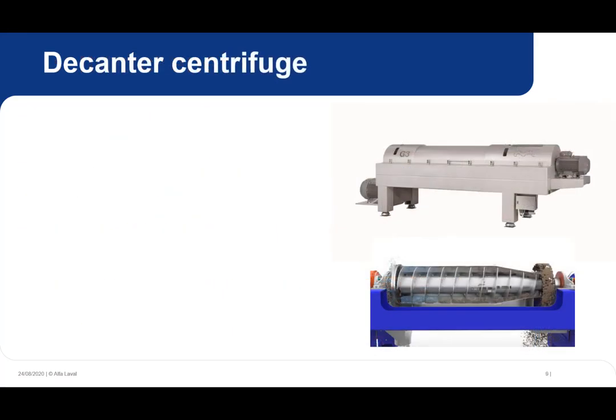A decanter centrifuge is the final thickening method we'll talk about. It operates by means of a horizontal cylindrical bowl equipped with a scroll conveyor that rotates at a high rate of speed. The feed enters a centrifuge through a stationary inlet tube in the center and is accelerated into the bowl by a distributor. We call this distribution area the feed zone. The bowl and conveyor rotate at a slightly different speed, allowing the conveyor to push cake solids up the inclined cone of the bowl, also called a beach, and out, while the clean centrate exits the other end of the centrifuge. The components exposed to liquid are often protected by replaceable parts made of something like tungsten carbide.